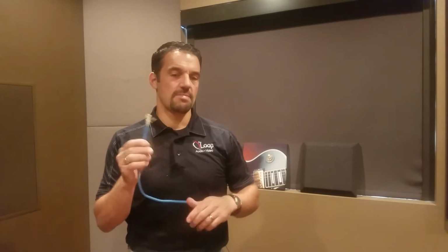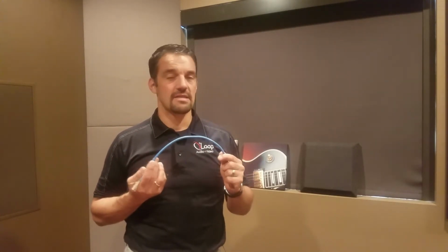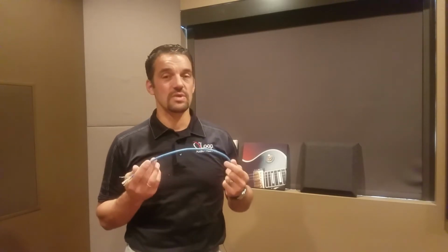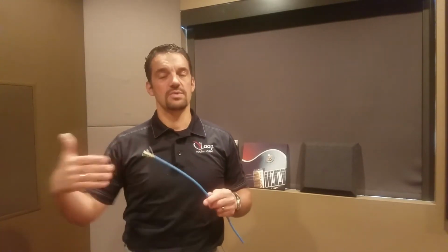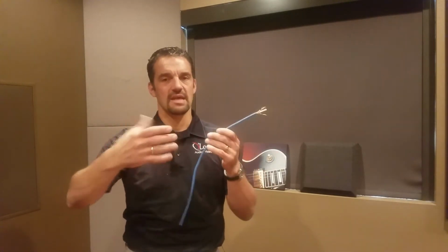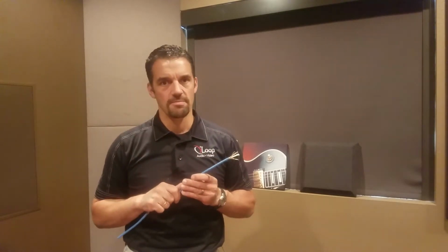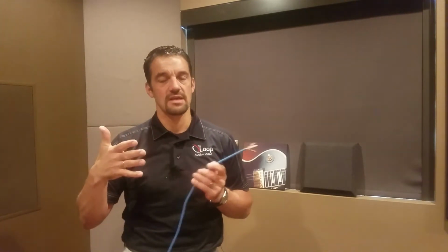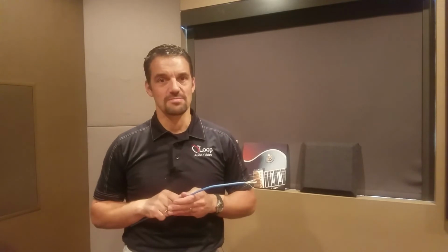So it takes a lot longer to put on that connector. That doesn't seem like that big of a deal, but what if you have 50 or 80 runs of Cat 6? That means there can be 100 to 160 connectors. Now we're starting to talk about hundreds of dollars in additional labor. If you're spending $10,000 on your pre-wire, not a big deal. That's again why it's more important in commercial, because the projects are so much more intense that the cost delta is quite small, and they need those higher speeds to make sure their employees can work as efficiently as possible.